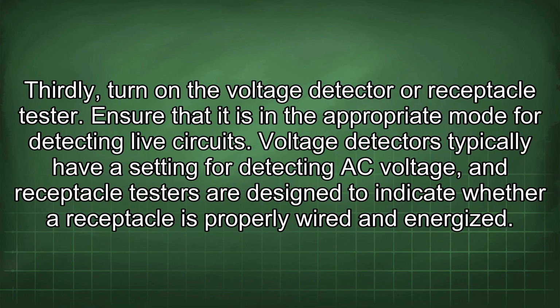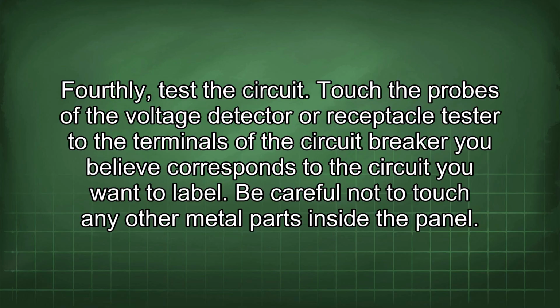Thirdly, turn on the voltage detector or receptacle tester. Ensure that it is in the appropriate mode for detecting live circuits. Voltage detectors typically have a setting for detecting AC voltage, and receptacle testers are designed to indicate whether a receptacle is properly wired and energized. Fourthly, test the circuit. Touch the probes of the voltage detector or receptacle tester to the terminals of the circuit breaker you believe corresponds to the circuit you want to label. Be careful not to touch any other metal parts inside the panel.